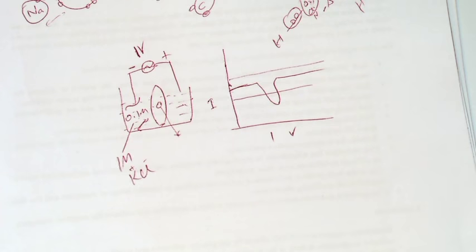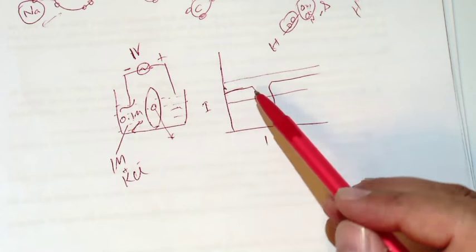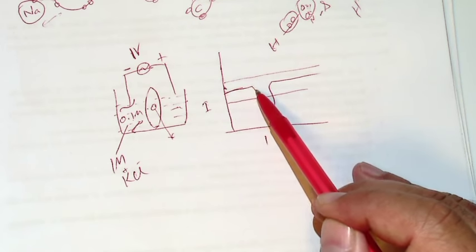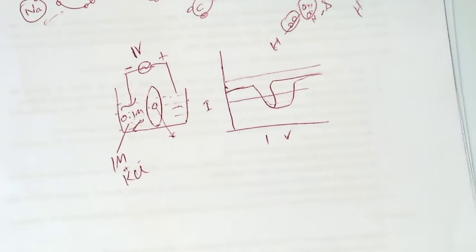Now, if one DNA is longer than the other one, what do you expect? We expect that in that case, we might have a longer dip, right? So by looking at the shape of the dip, we can identify whether the DNA is long or not, and from the ratio, we can understand the approximate length of the DNA, right? So that information we can get very easily. And it's very straightforward. It's very easy to operate the equipment, the setup. As compared to other methods, we don't have to use any fluorescent dyes.